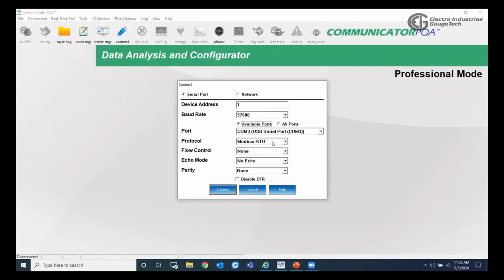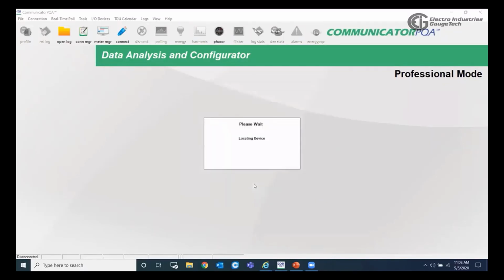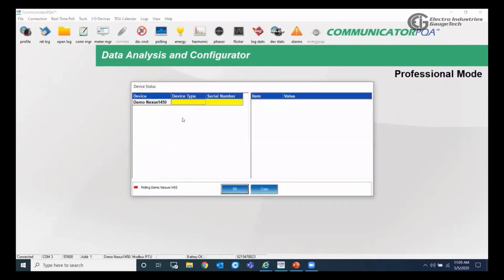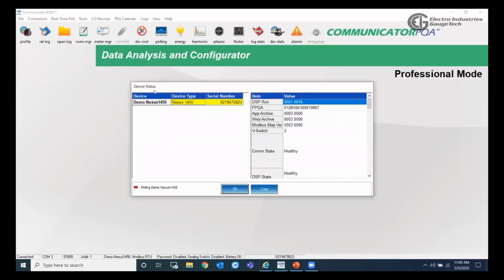And then the protocol, which is Modbus RTU, and the other options, which would be matching with the port settings. So we have the flow control none, the echo mode is no echo, and the parity is none. I will hit connect. And once I'm connected, the device status window will pop up like this.